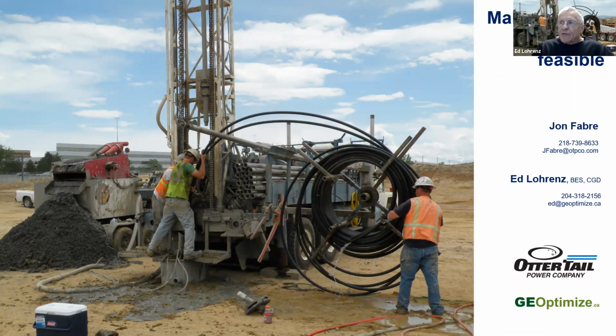Where I've seen that work, we actually did a feasibility study for a project in Kerala province of India. Ground temperature is about 83, 84 degrees. And when we did the energy modeling for that building, the winter design temperature was about 70 degrees Fahrenheit. And the dialog box came up in the energy modeling software: are you certain that this energy model, the weather data that you have imported, is accurate? So yeah, the ground temperature is really high.